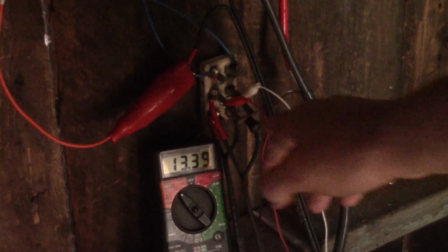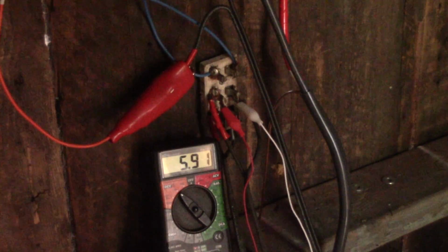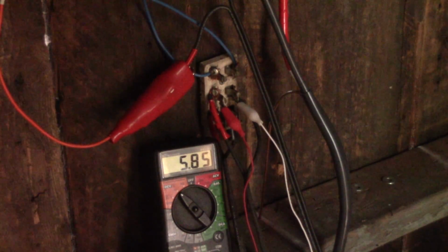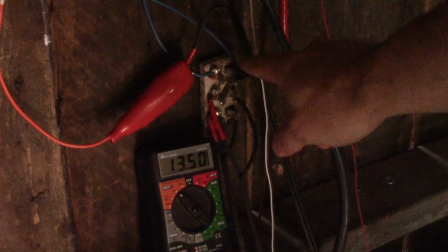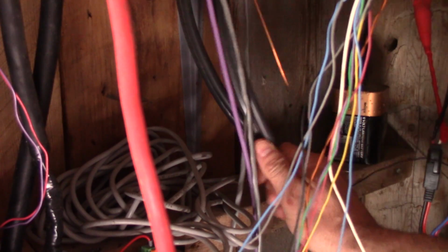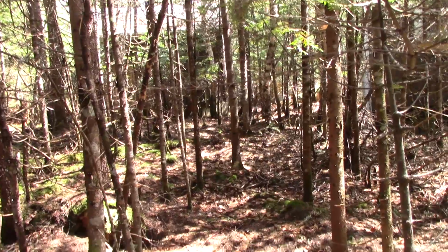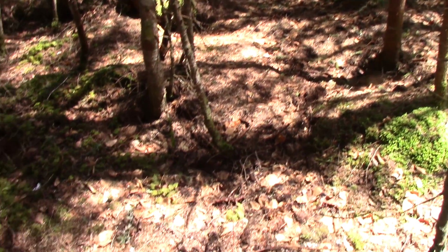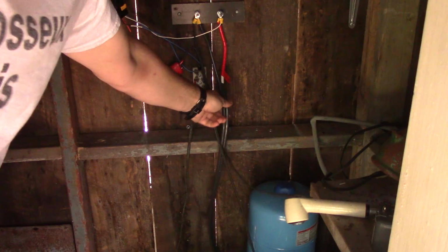And if I check this with a voltmeter, I can clearly see that with my 16-gauge wire, the voltage drop is close to 7.6 volts. And the voltage drop with the number 8 wire is also close to my calculation. So that's the reason why I've added this number 8 gauge wire from the main shed through a trench that René dug, and the wire ends up inside the watershed.